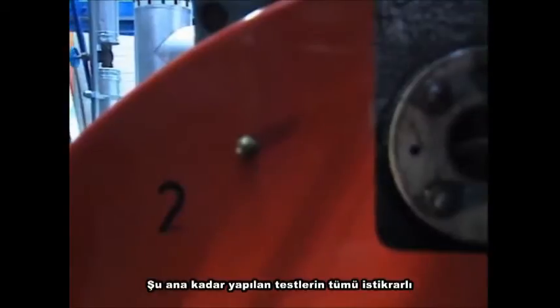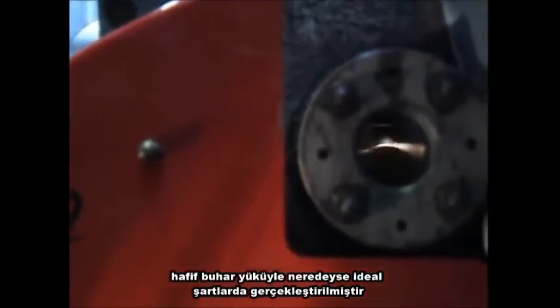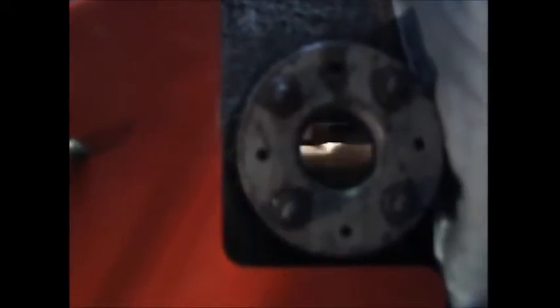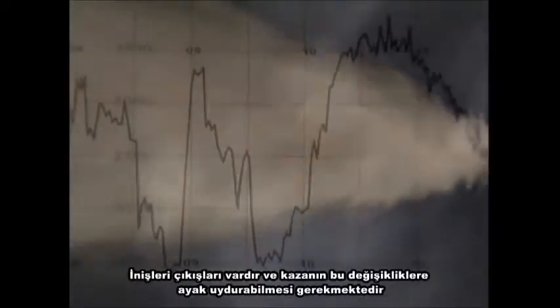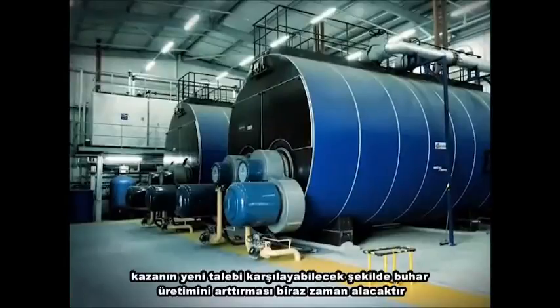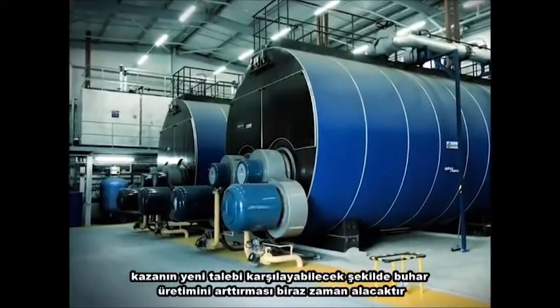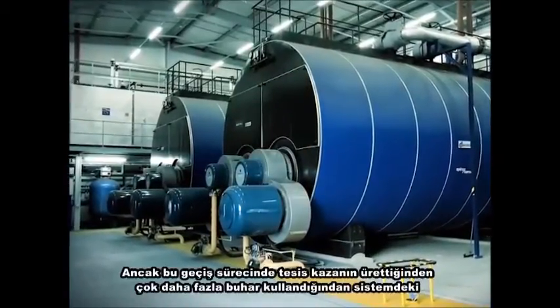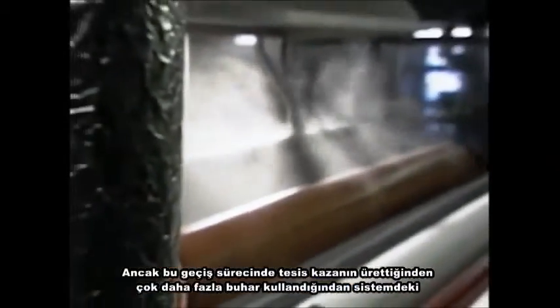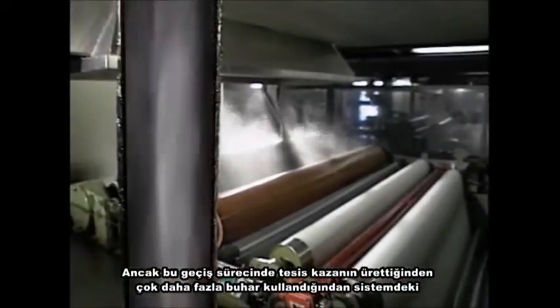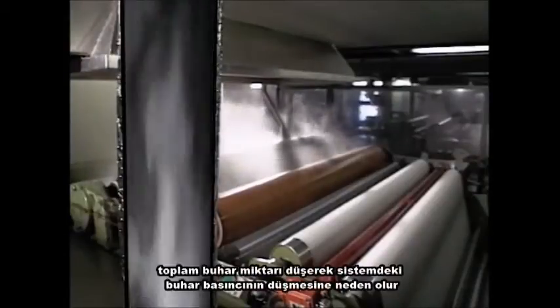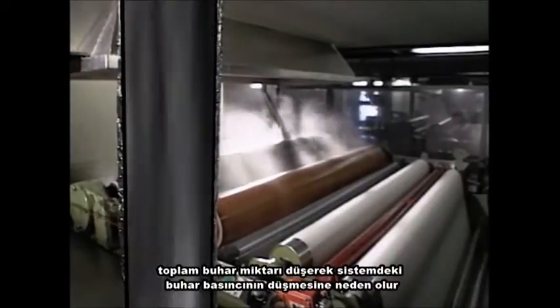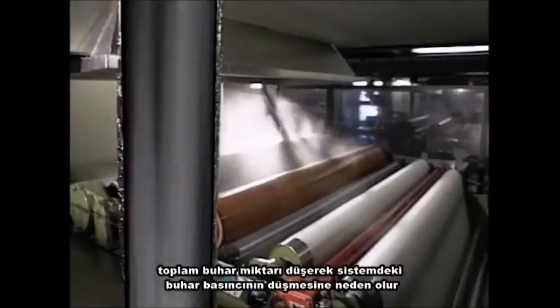All of the tests so far have been conducted in almost ideal conditions with a steady light steam load. However, in reality, steam demand is rarely steady. It comes in peaks and troughs, and the boiler must be able to respond to these changes. Whenever the steam demand increases, it will take a little time for the boiler to raise its output to match the new demand. However, during this transition period, more steam is being used by the plant than the boiler is producing, so the total amount of steam in the system falls, which causes the pressure in the system to drop.